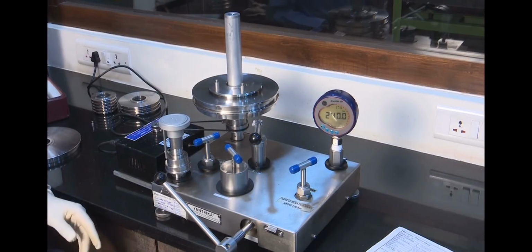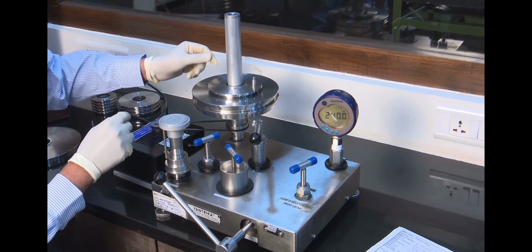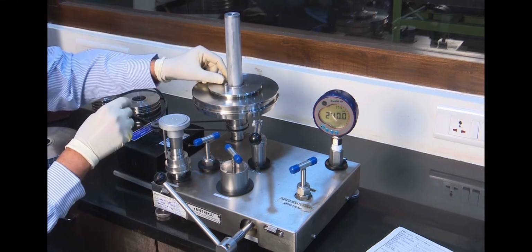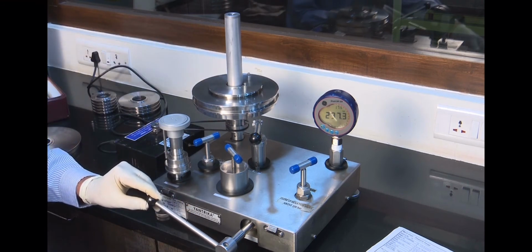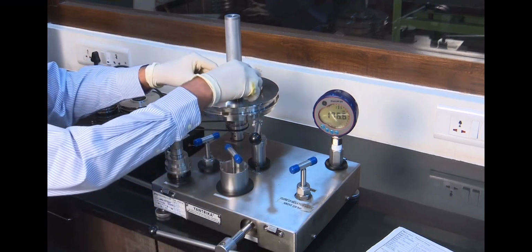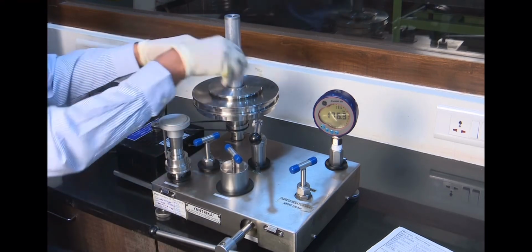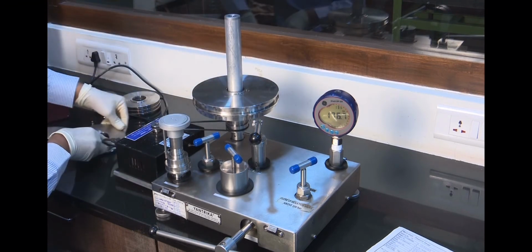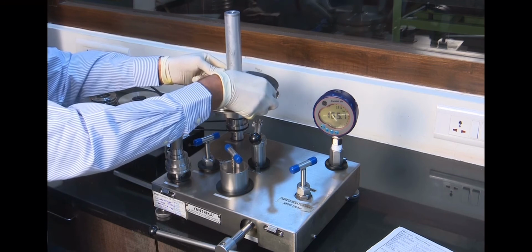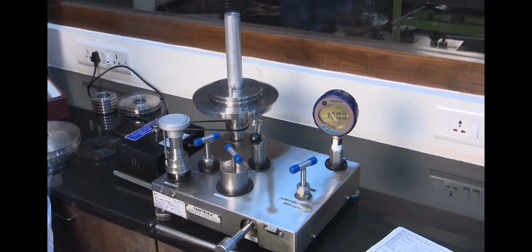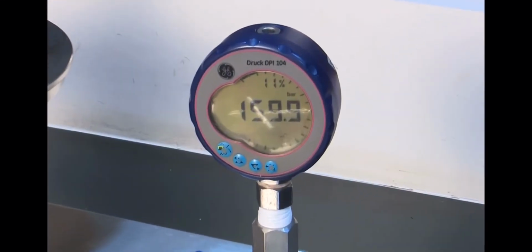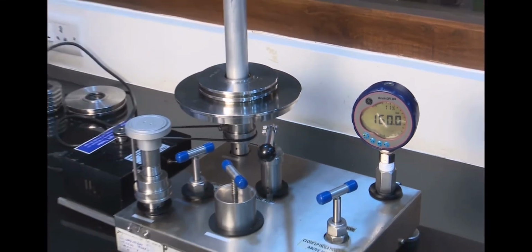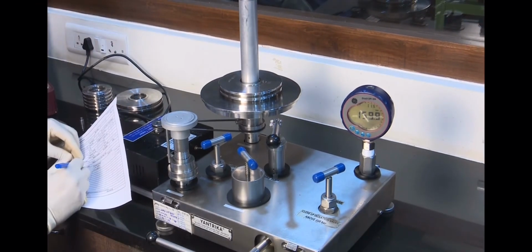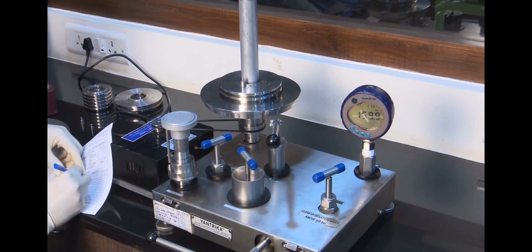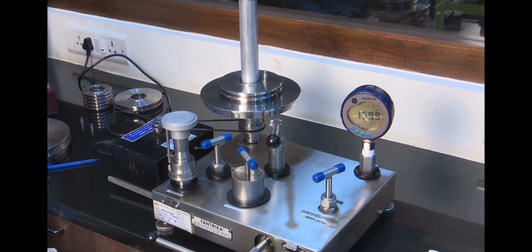For decreasing cycle, I have already placed weight for 240 bar calibration point. Now I am demonstrating 160 bar calibration point for decreasing cycle. Remove the weight until the UUC shows 160 bar. Allow it to stabilize for 30 seconds. Now record the value of weight adjusted on dead weight tester against the UUC. Similarly, we can perform calibration for other calibration points for decreasing cycle.